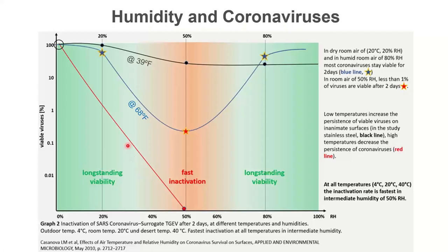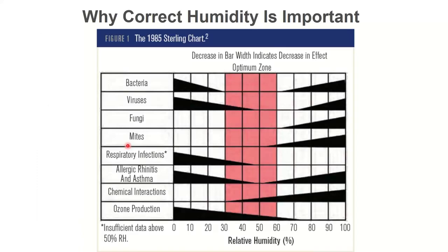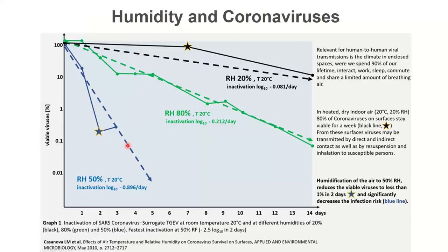I'll just show you. I won't repeat them, but I'll show you what those two charts look like. That was the Sterling chart I was talking about, where everything bad happens below 30 or 40% humidity, and other bad things happen above 60. This is out of the ASHRAE handbook. So 40 to 60 is a sweet spot.